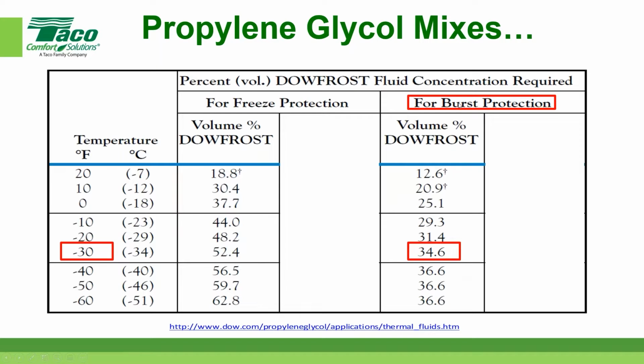If I were just worried about the fluid actually expanding to the point of bursting my pipes or my heat exchanger, I really only need about 35% mixture. Okay, and look down here, this looks like a typo, just repetitive numbers. In reality, you never need more than 36.6% glycol if you're worried about bursting your pipes. So anyway, just a heads up on that. And that's not part of your handouts.